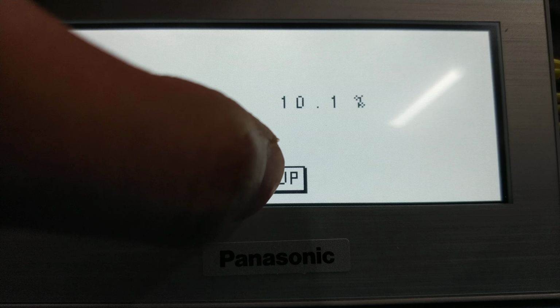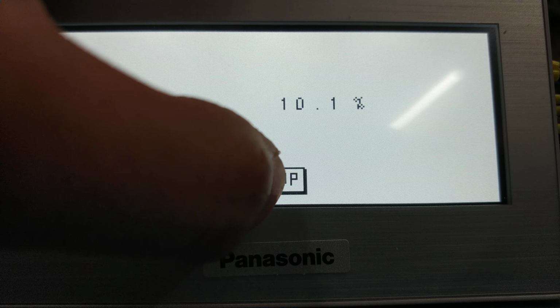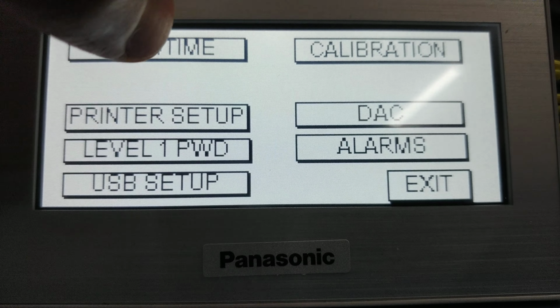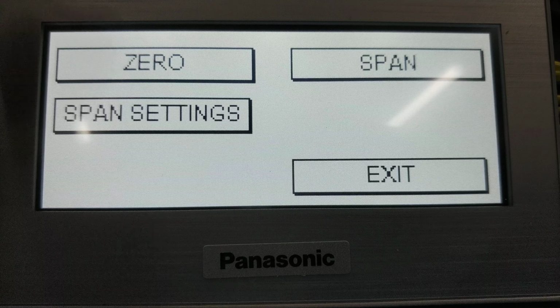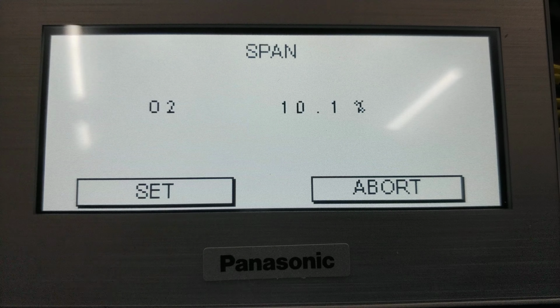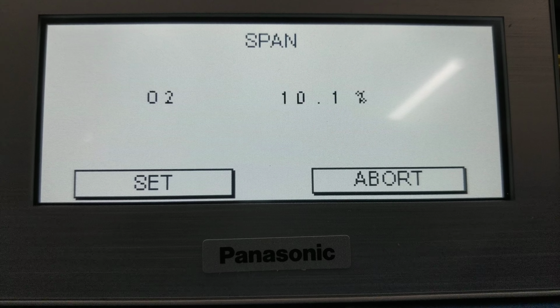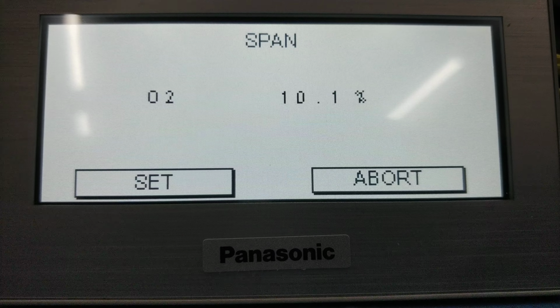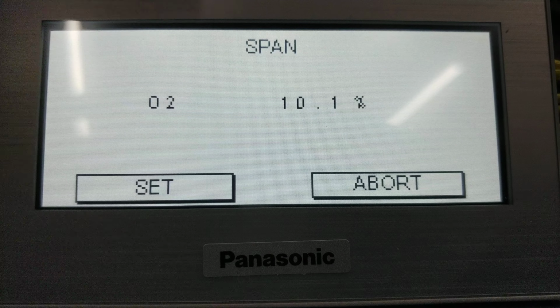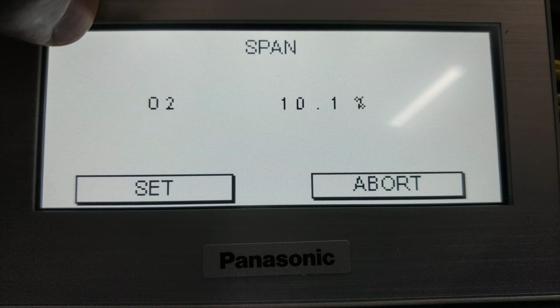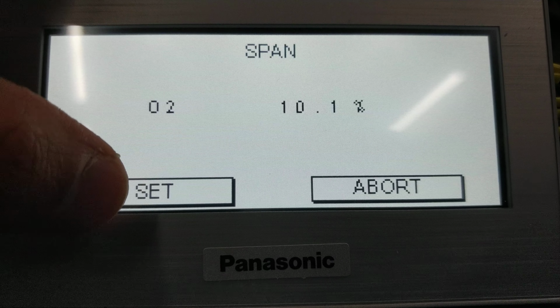So now we're going to go ahead and do a span calibration. We're going to go to setup, calibration, and then we're going to hit span. And let it go for a couple minutes. Let the sample gas go through the system if you haven't already done so. Once you do that, you're just going to hit set here.